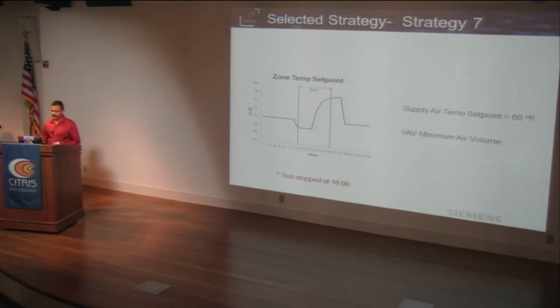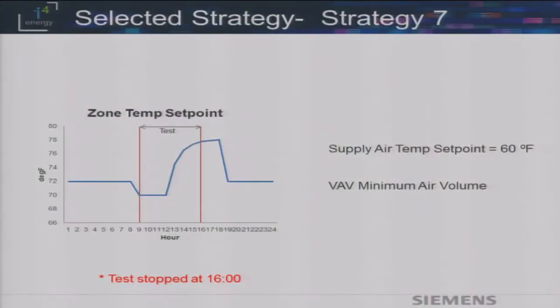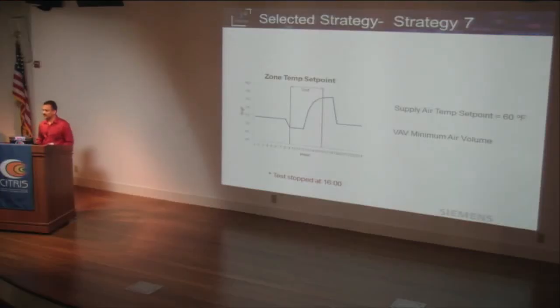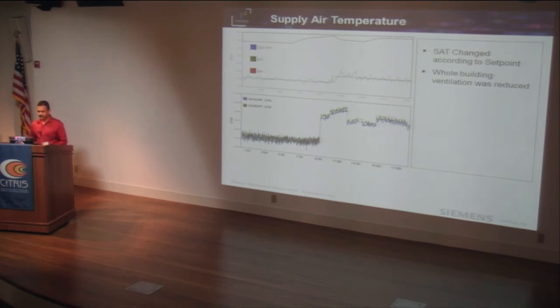Out of those, strategy 7 was selected, which has the temperature set point going near 78, 77 something. We pre-cooled from 9 a.m. until 12, and then we raised the set points exponentially, and we changed the minimum airflow. We thought the test was supposed to stop at 4, but due to other technical reasons, we stopped at 3 p.m. The supply temperature was also changed. Until 9 o'clock, it was 57.5, which was the earlier set point, and then we raised the set point to 60.